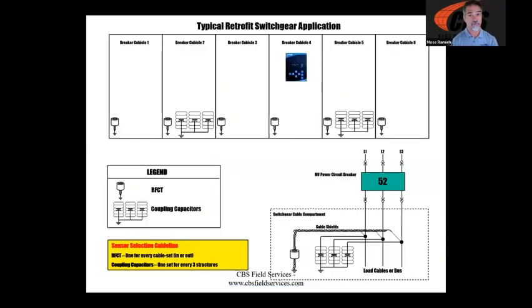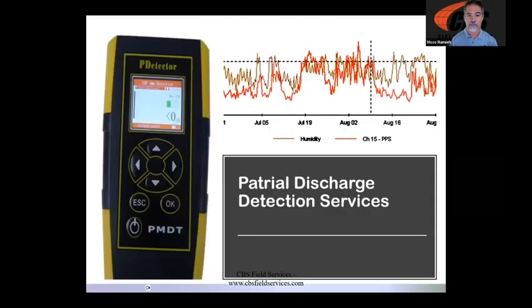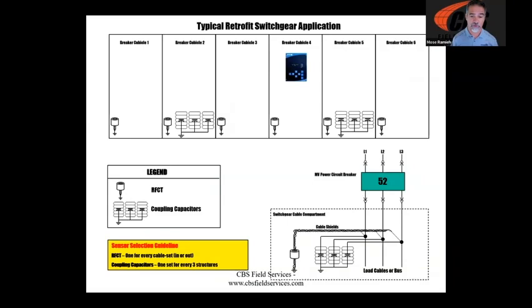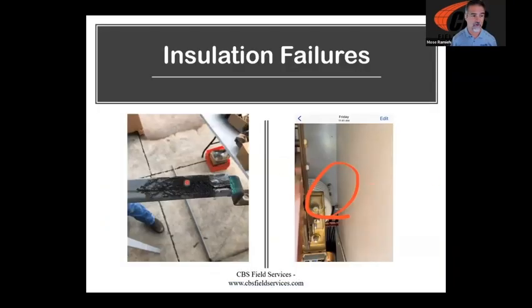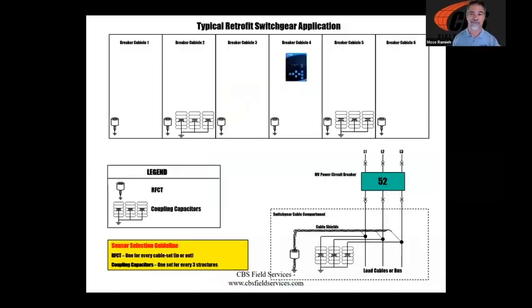The other thing is, once again, if you have a supercritical system, I'd love to actually have a client put one of these in so that I could actually see how it all comes together. But the nice thing about a continuous online system, going back to the previous slide, is that it gives us this data trended all the time, right? If we use a handheld device, it's kind of one and done. We're gonna come in, check it this month, or check it next month, or check it once a year. It's one sample in time, right? We might sample on a day where our PD is really low. We might sample on a day where our PD is really high. But once again, we don't know where we're at without that continuous monitoring, or at least something more frequent than annual. So once again, that's a great way to head off the problems that start off as partial discharge. So anything that's creating some partial discharge and damaging our equipment, PD is a great way to find that. And obviously continuous PD is the best way.